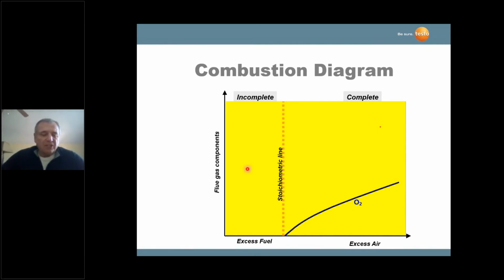If you look at this combustion diagram, we have two sides of it. Incomplete, which we just talked about, which means excess fuel. On the complete side, we have excess air. So what we're saying is we want to stay on the complete side. And as we add more and more air to the burner, or if we adjust the air and fuel ratio and we add more air, what happens to the O2 in the flue gases? Well, it's going to go up.